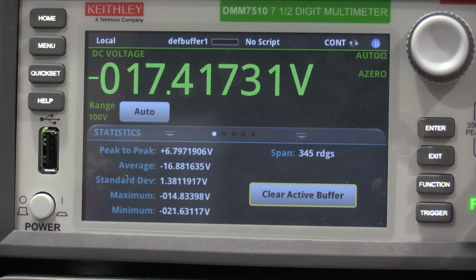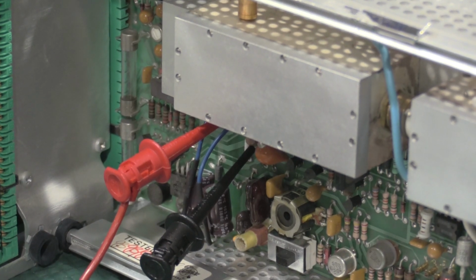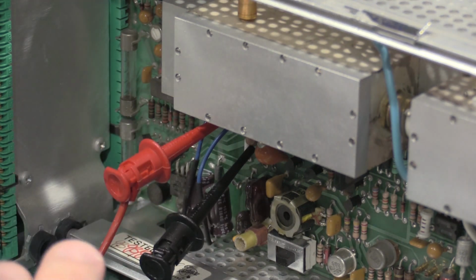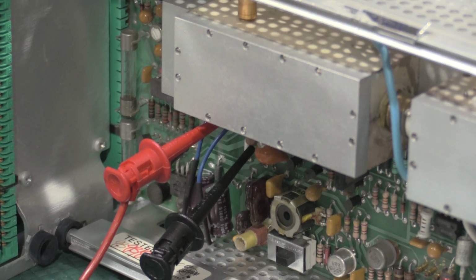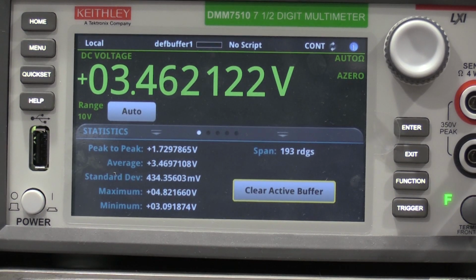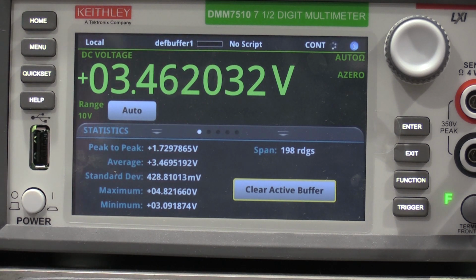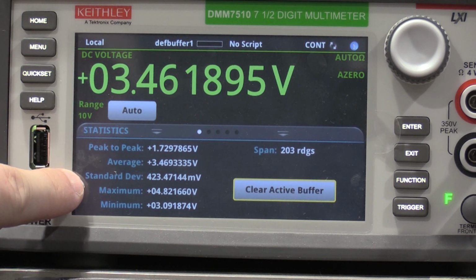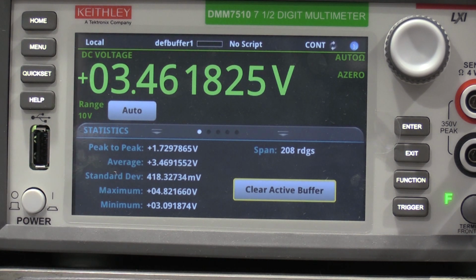And then we'll need to play with the spectrum analyzer a little bit. Okay, for this one, the digital multimeter goes across our 615 again. I'm a little bit ahead of myself checking the high range, but it goes across our 615. I have to wind it down the scale, and I need half a volt below 5.182 for this to be in spec. All right, again, using the meter to my advantage and doing some statistics, we have a maximum of 4.8 and a minimum of 3.09, so we are good.